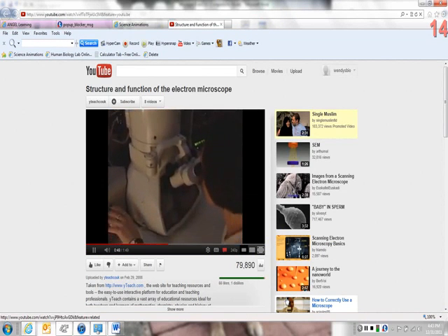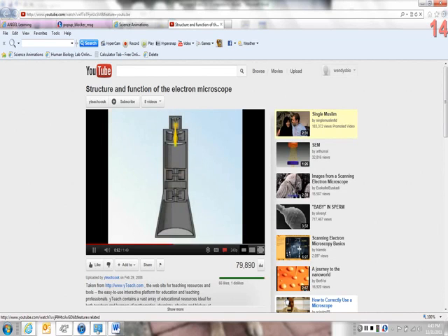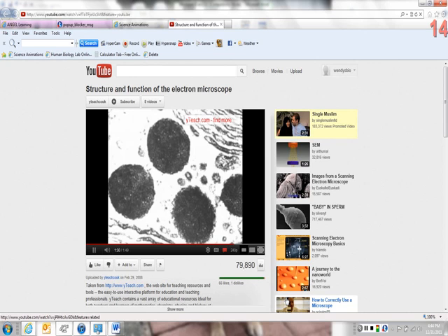The beam is maintained along the tube by means of electromagnetic lenses. These are coils that surround the tube at given intervals. The electromagnetic field emitted by the coils focuses the beam at the center of the tube. Electrons encounter the specimen and are either absorbed, scattered, or pass through it. Because different regions of the specimen are variously transparent to electrons, different amounts of electrons, with changed energy, pass through these regions. At the end of the tube, the electrons are collected on fluorescent or photographic film, or on screens that generate an image of the specimen.